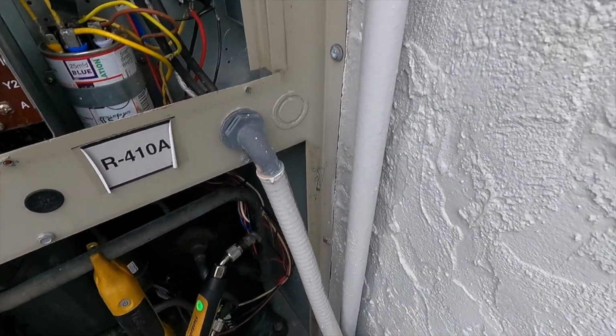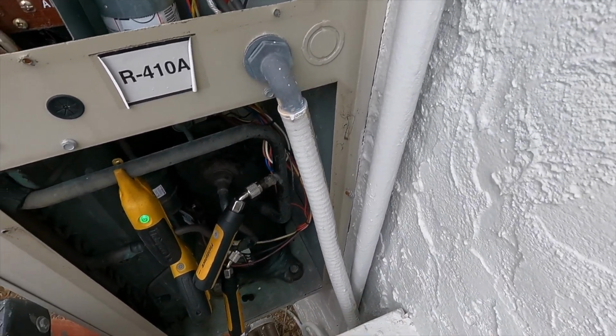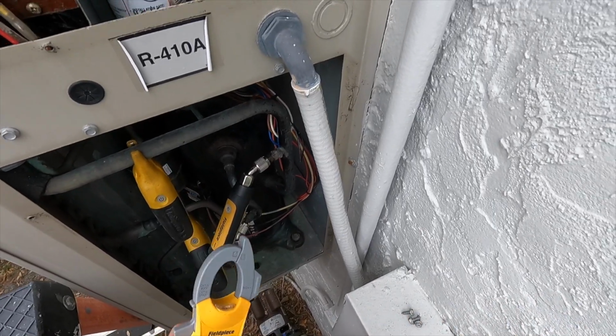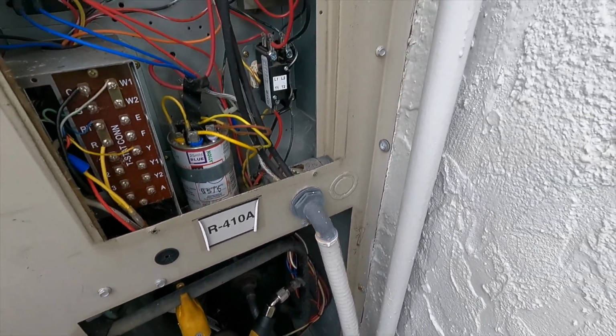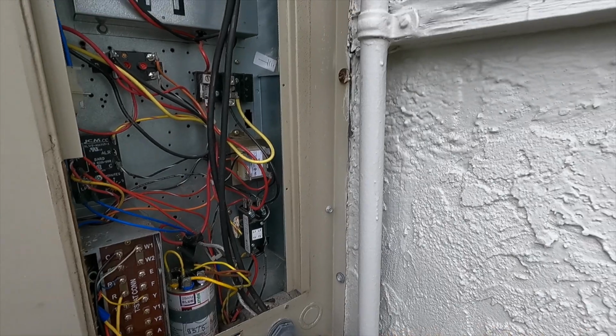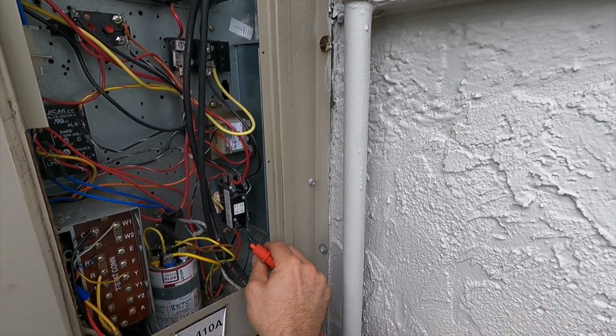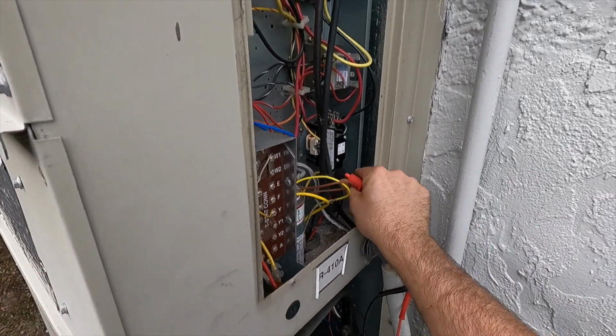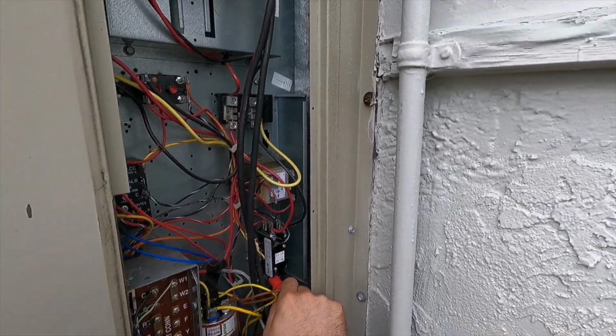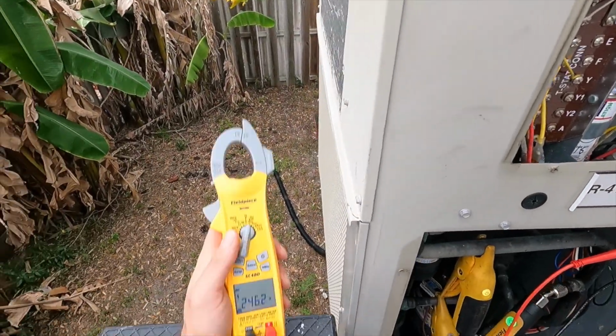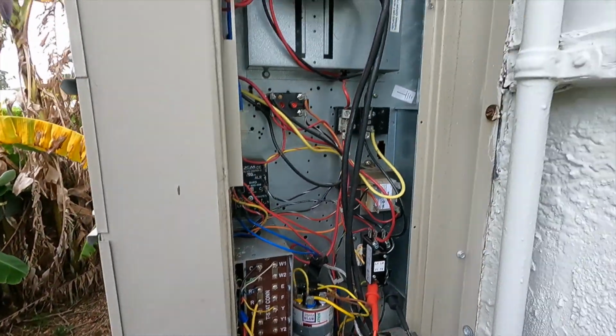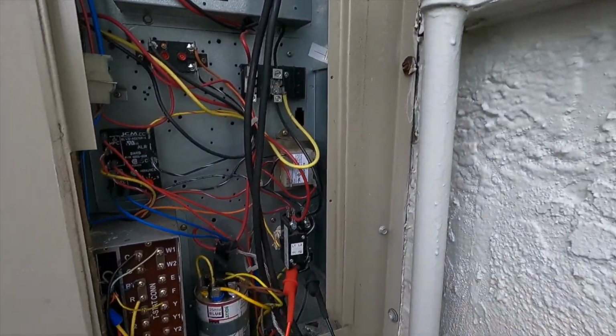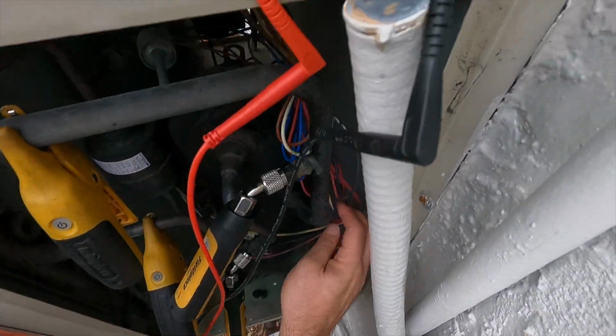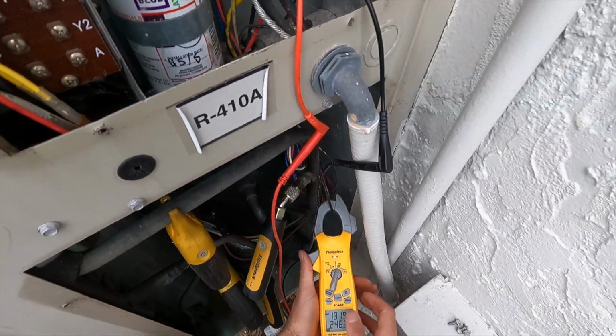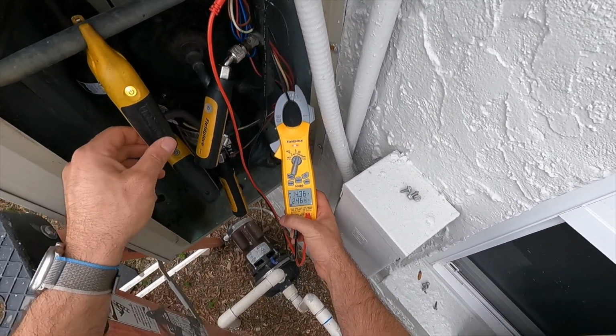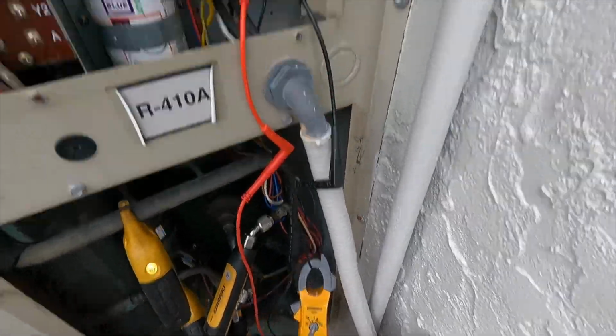Again, we can go ahead and just check our high voltage supply, make sure it's proper, looking good. Not a necessity, but you know, system's obviously got 240, it's operating. But I like to be thorough, so why not? We'll just put it on the bottom tab there, top tab there, 246. Let's go ahead and take a compressor amp draw. 14.3 on our compressor amps.